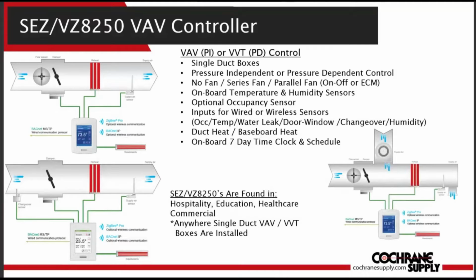These controllers are used to control single duct VAV and VVT boxes, or any package zone control, damper, an airflow ring or sensor in the case of a VAV box, preheat, duct, baseboard, or both, and possibly a series or parallel fan. The 8250 can be configured to operate modulating, which are 0 to 10 volt DC, or floating damper actuators. They can also be configured to operate duct and baseboard heat. That can be either hot water or electric. The signal to engage that heat can be modulating, on-off, floating, or pulse width modulation.